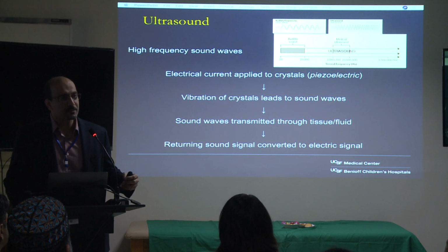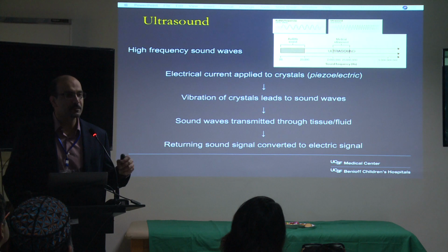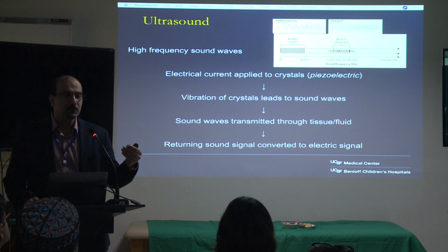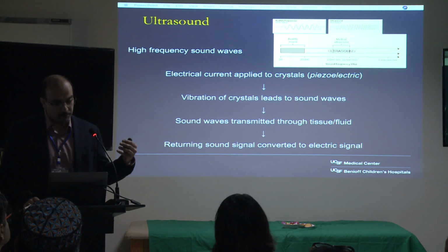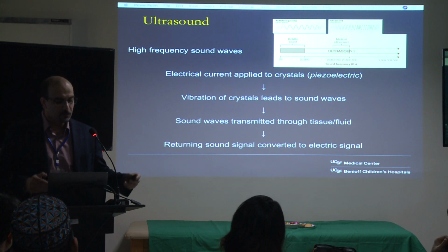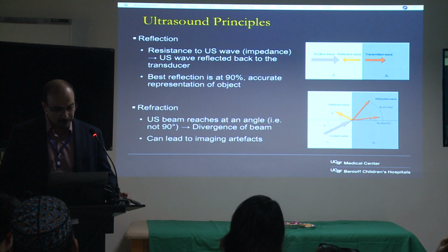And how is it generated? You have these piezoelectric crystals that, once stimulated with an electrical current, create vibrations, and those transmitted vibrations are turned into an ultrasound signal. Basically, as that signal hits a structure, it is either reflected back, absorbed, or goes through. Based on what's reflected back is what we get as our ultrasound coming back, and that's converted back into an electric signal. So you've closed the loop, and that's how you create the image. And I'll get into that a bit more.